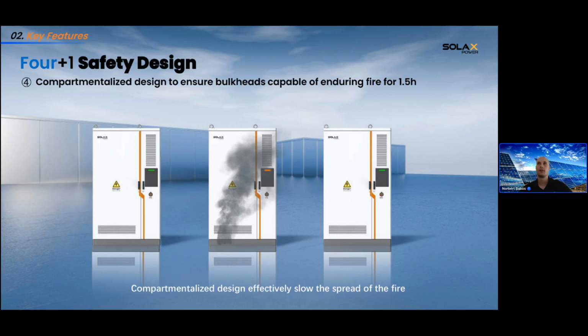And the fourth level is if it's still not enough and you still have fire inside the ESS, the whole shell is designed to hold the fire inside the cabinet for 1.5 hours. This is because obviously if you cannot suppress the fire within the ESS, you will call the firefighters to come on site and do their job. That's why it has a 1.5 hour fire resistance, to prevent the fire from spreading to other devices you have near the ESS.